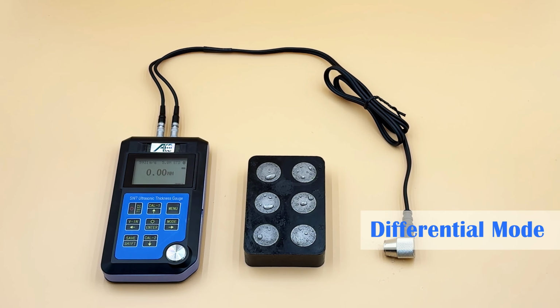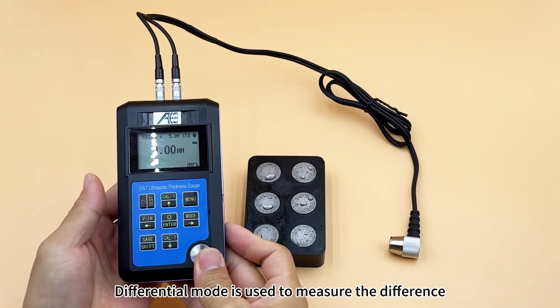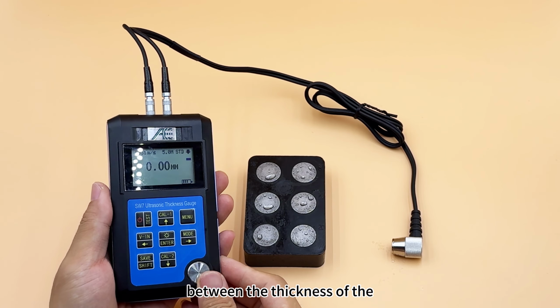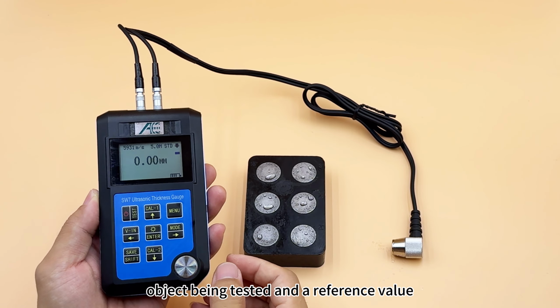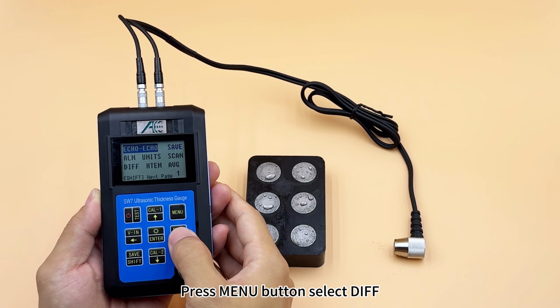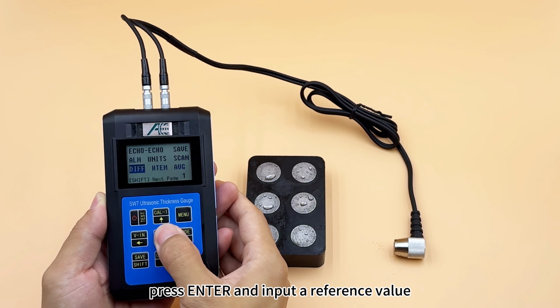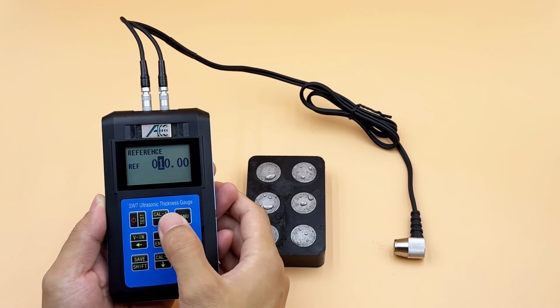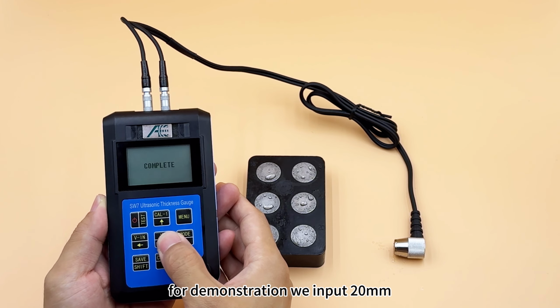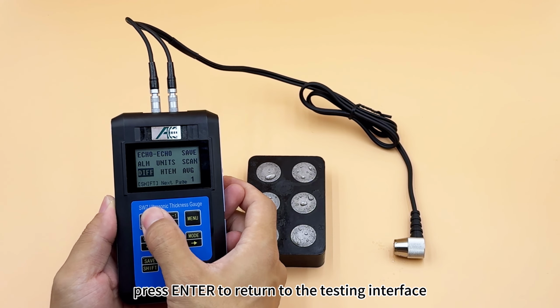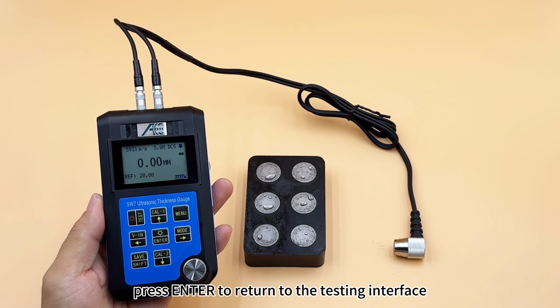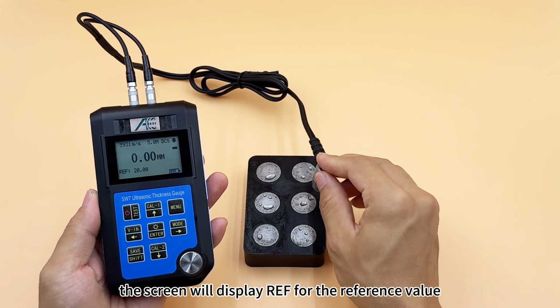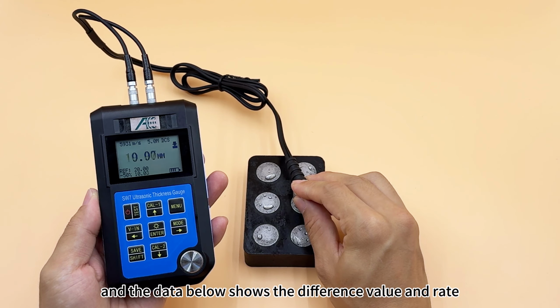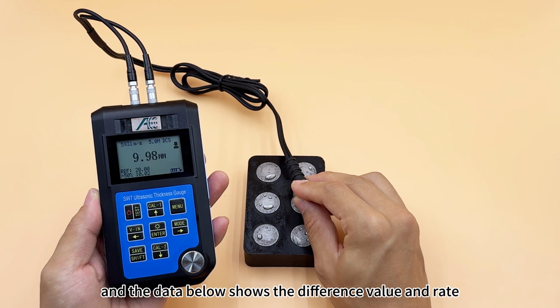Differential mode. Differential mode is used to measure the difference between the thickness of the object being tested and a reference value. Press Menu button, select Diff, press Enter, and input a reference value. For demonstration, we input 20 mm, press Enter to return to the testing interface. The screen will display REF for the reference value, and the data below shows the difference value and rate.